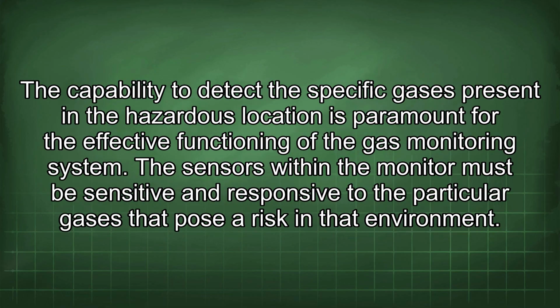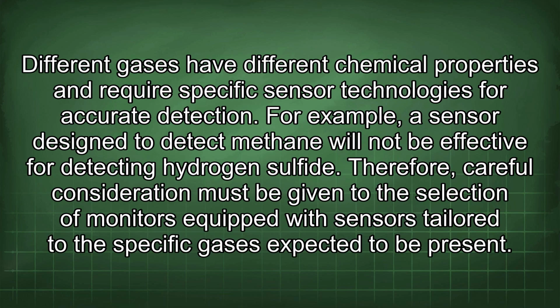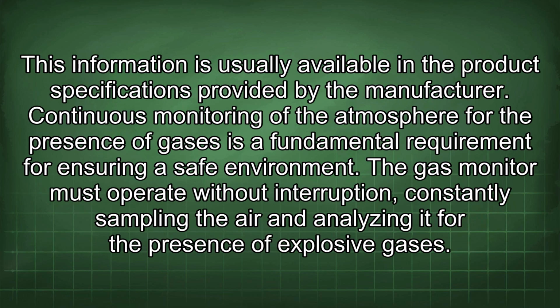The capability to detect the specific gases present in the hazardous location is paramount for the effective functioning of the gas monitoring system. The sensors within the monitor must be sensitive and responsive to the particular gases that pose a risk in that environment. Different gases have different chemical properties and require specific sensor technologies for accurate detection. For example, a sensor designed to detect methane will not be effective for detecting hydrogen sulfide. Therefore, careful consideration must be given to the selection of monitors equipped with sensors tailored to the specific gases expected to be present. This information is usually available in the product specifications provided by the manufacturer.